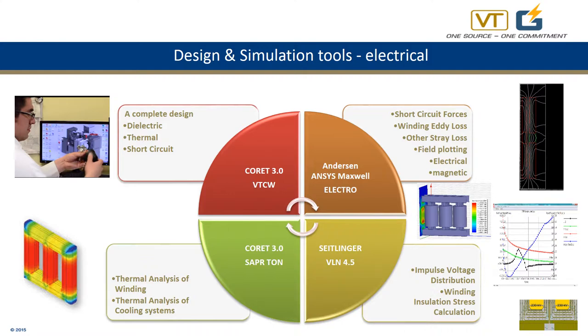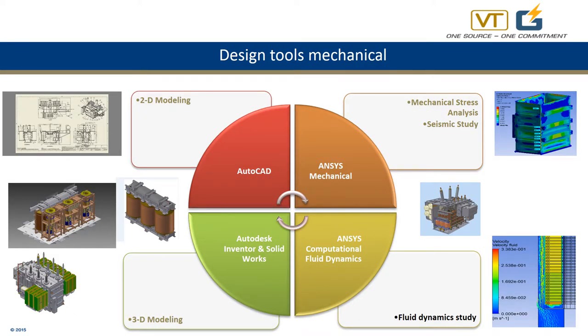So we have CORET and VTCW for design. Andersen, ANSYS, Electro, and Maxwell are simulation tools used to calculate and check short circuit forces, eddy losses, and stray losses, and then Seitlinger, as we discussed, checks impulse voltage distribution and winding insulation stress. SAPR TON is another tool for thermal analysis, and for mechanical design we have several tools such as AutoCAD and Autodesk. One notable feature of our ANSYS use is that it checks the fluid flow through cooling ducts to ensure proper cooling.